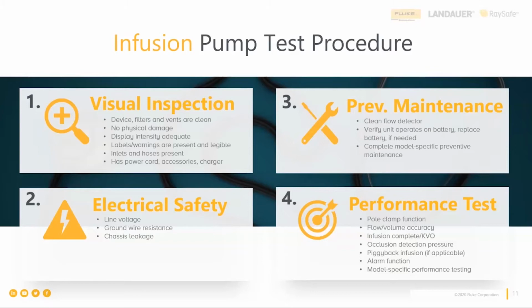Like I said before, infusion pumps require preventative maintenance at least once a year. Hospitals generally test infusion pumps at incoming inspection, for scheduled PMs, and post-repair. And OEMs test infusion pumps for quality control. Preventative maintenance also includes verifying the pump is administering flow, volume, and boluses accurately and appropriately.